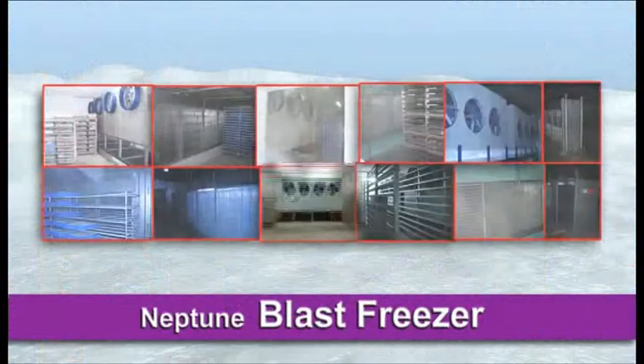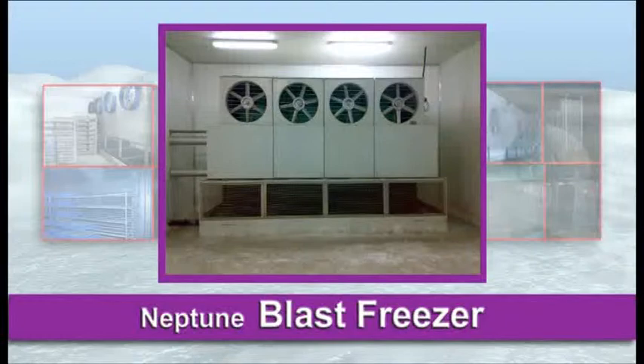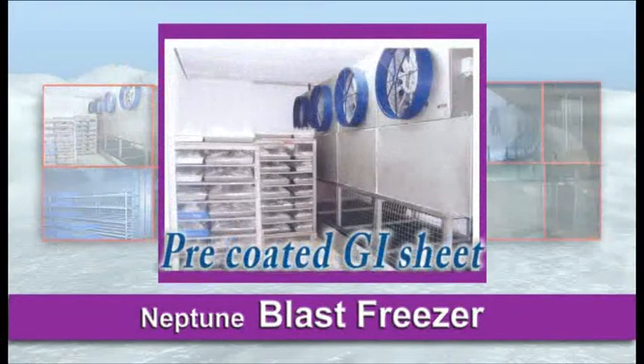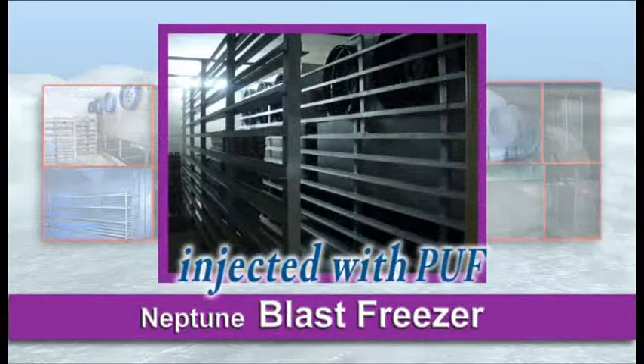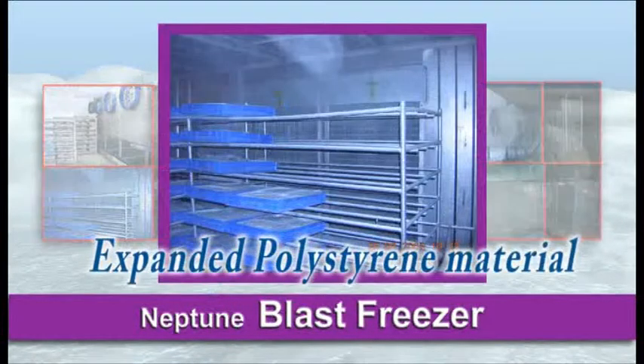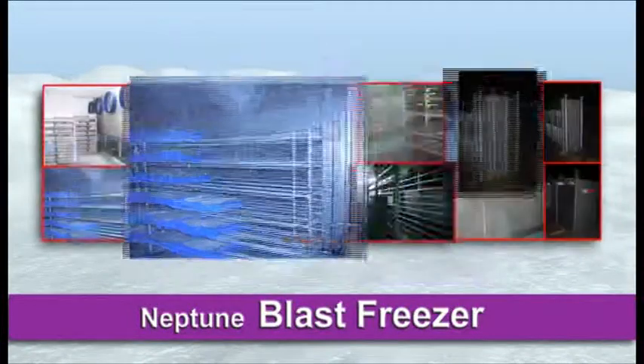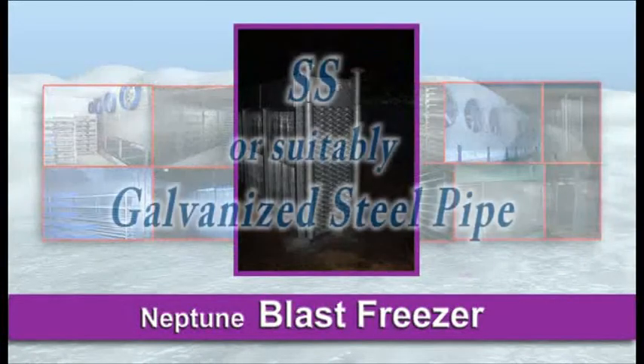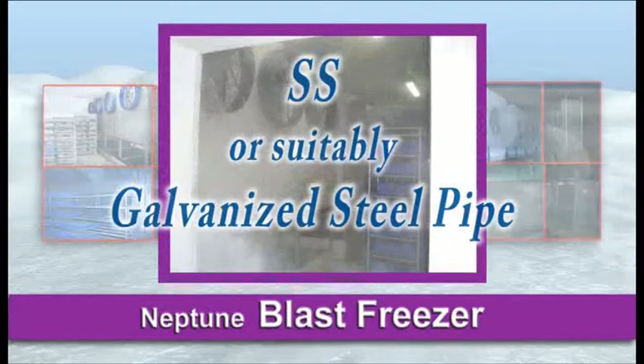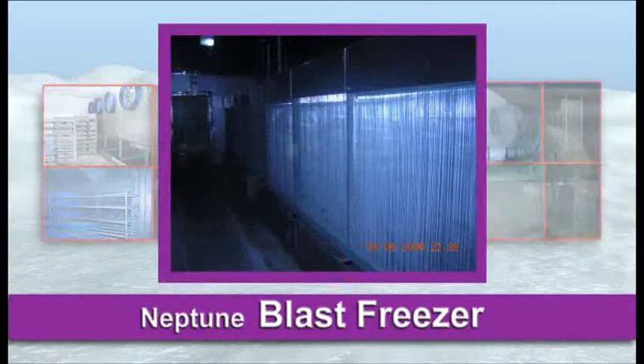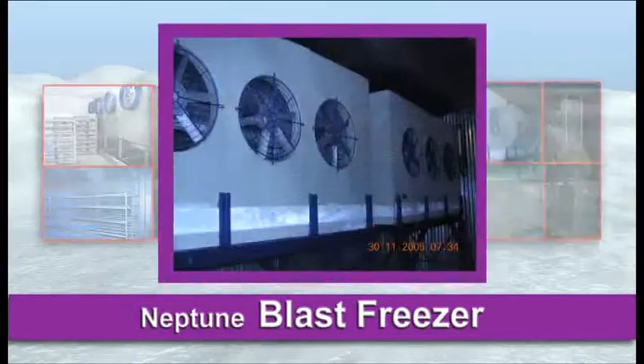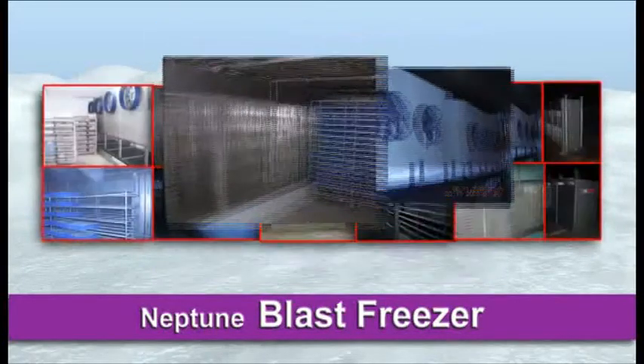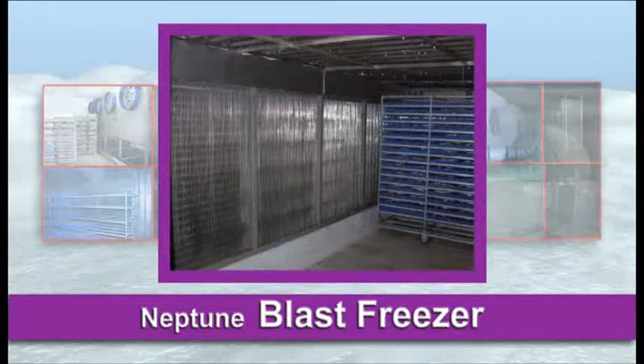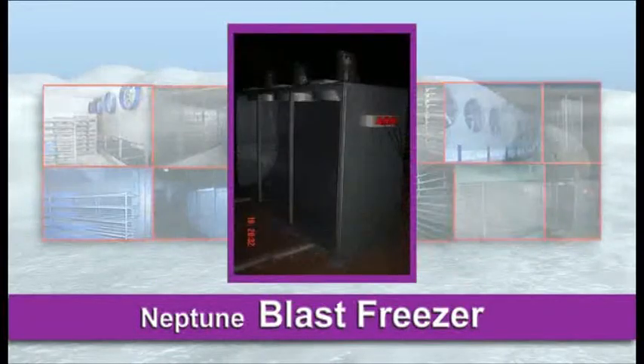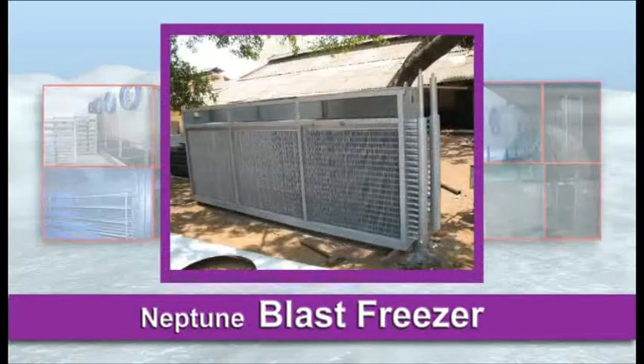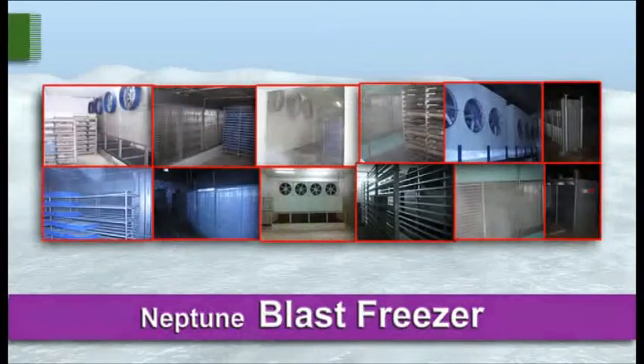Neptune blast freezer. The blast freezer room is fabricated with panels with either stainless steel or pre-coated GI sheet and injected with PUF or expanded polystyrene material. The blast freezer evaporator coil is fabricated from either SS or suitably galvanized steel pipe fitted with GI or aluminium fins. Cast aluminium axial fans are provided for proper circulation of air in the freezing zone. The blast freezer room is provided with an insulated door. Well-designed SS or aluminium trays are an option offered.